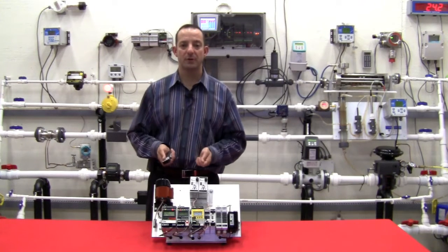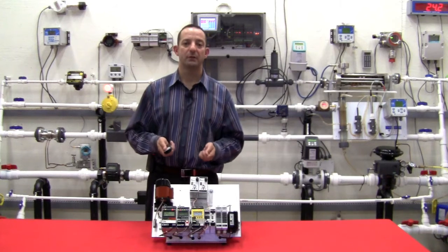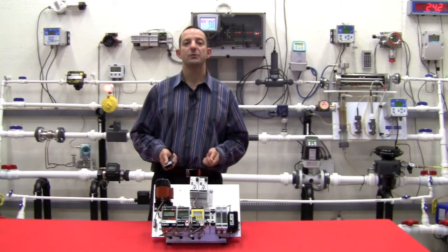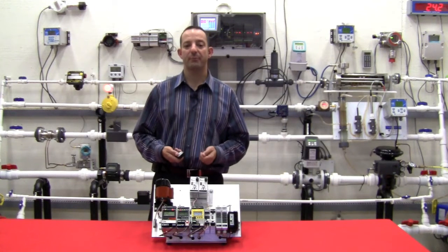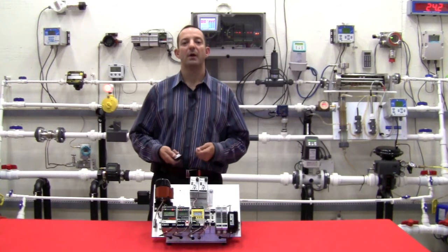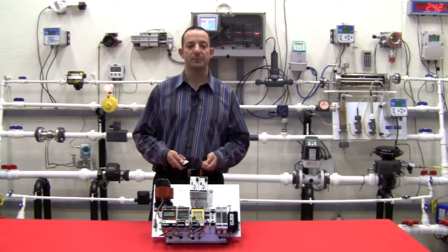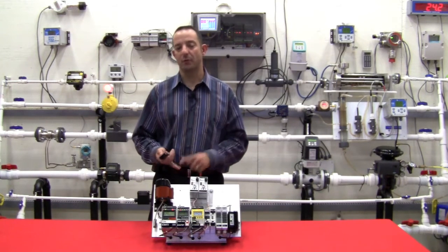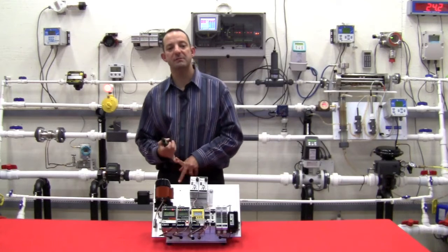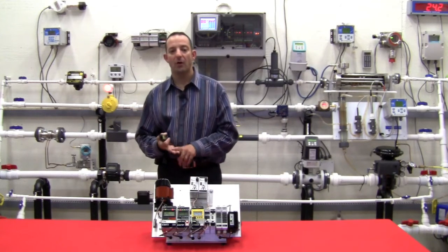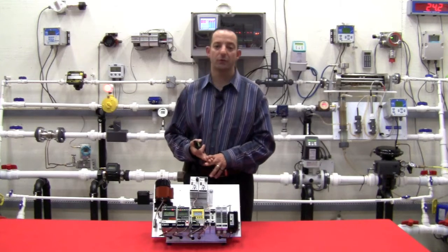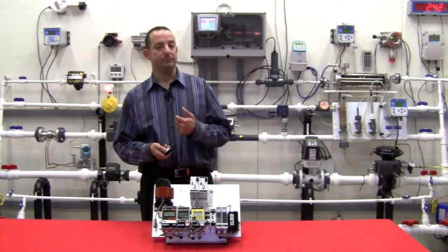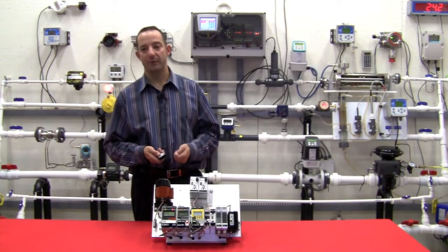A review of the alarm trip product family often includes a quick discussion of alarm trip basics. Alarm trips are used to warn of abnormal or unsafe process conditions. And we want to emphasize that our family of alarm trips can accommodate a wide variety of process signals, such as 4 to 20 milliamp loop currents, DC voltages, thermocouples, RTDs, resistance signals, or even AC currents. And our alarm trip family provides between 1 and 4 relay outputs.